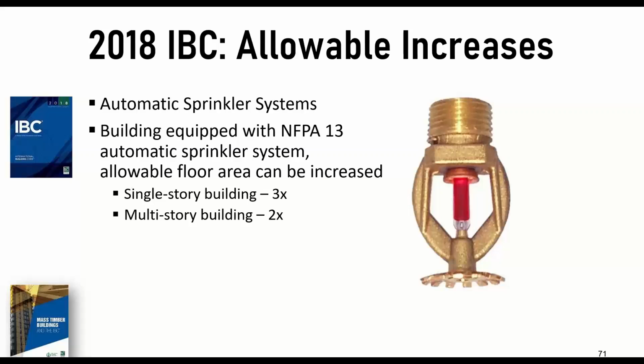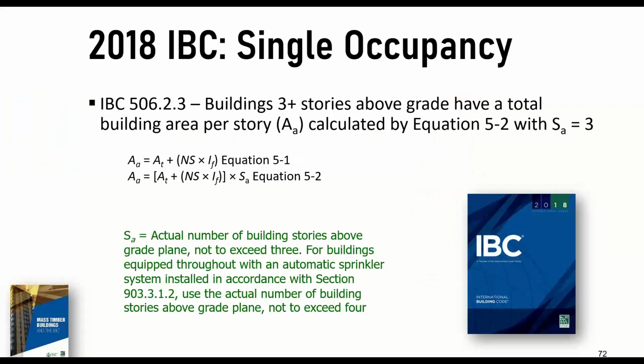occupancies. If you have an R occupancy, a residential occupancy, you have a similar height increase, but you don't get the allowable area increase if you're using the less than complete NFPA 13R. Again, 13R for residential compliant sprinkler system allows you to go up to 60 feet in height and 4 stories. Again, that's depicted in table 504.3 in the IBC.